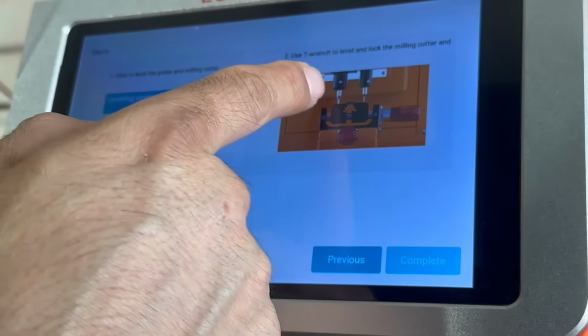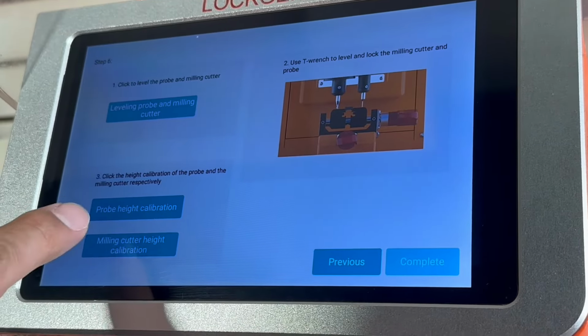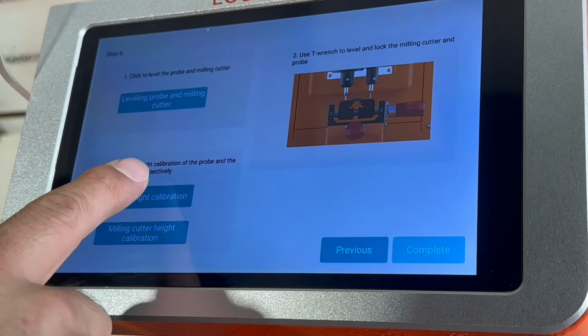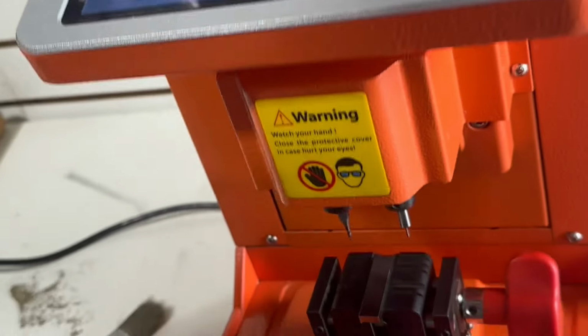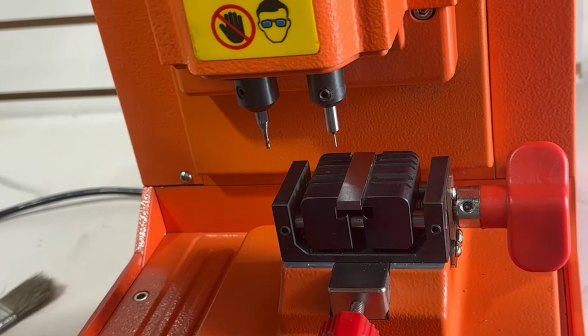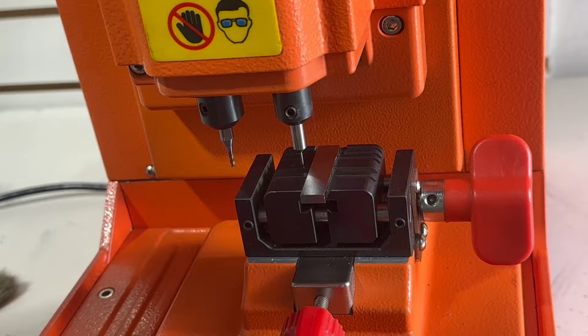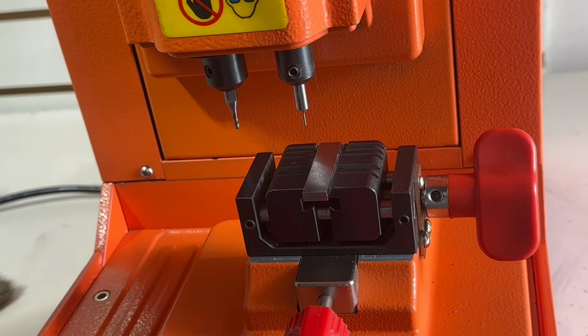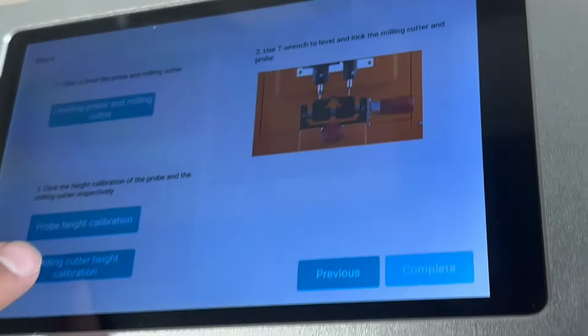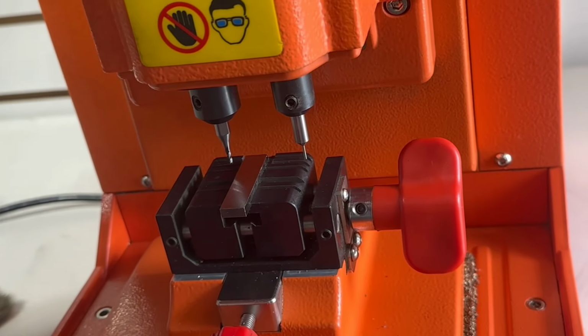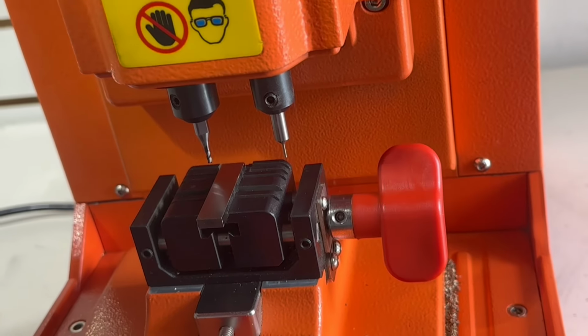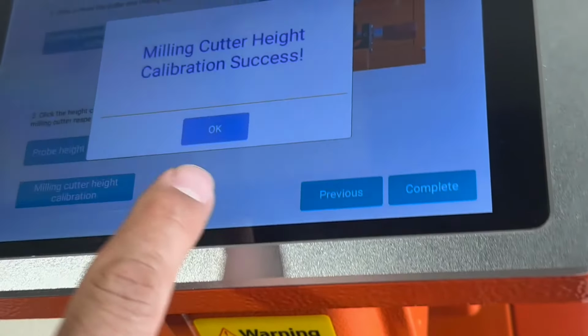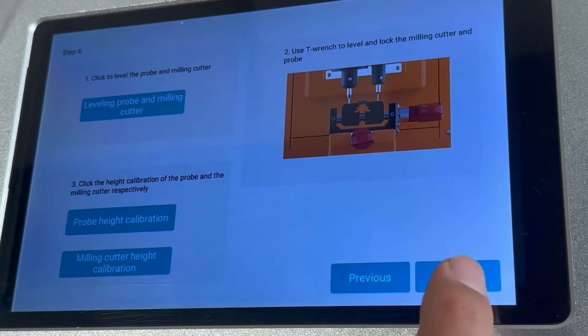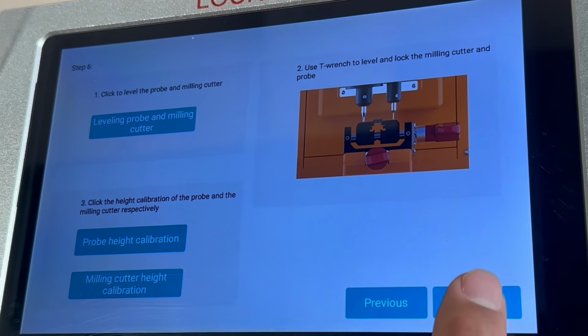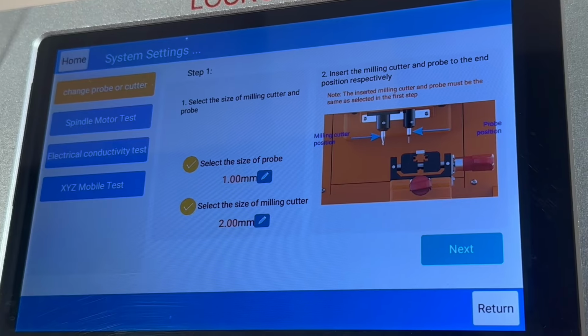So next step is to tighten, which we already did. Now it says probe height calibration. So we're going to do probe height calibration. So this is going to check the height of the probe as compared to the stage. Next, we're going to do the same thing for milling cutter. And we'll just go down and check the stage and make sure it touches properly. And once we see the success, you're going to press OK. And everything is done, you're going to press complete. So now your calibration is complete.